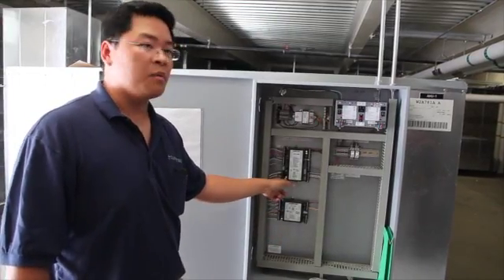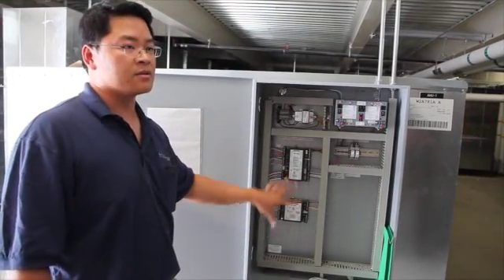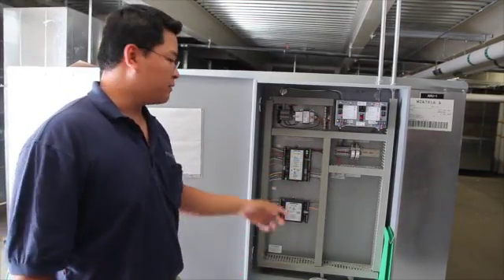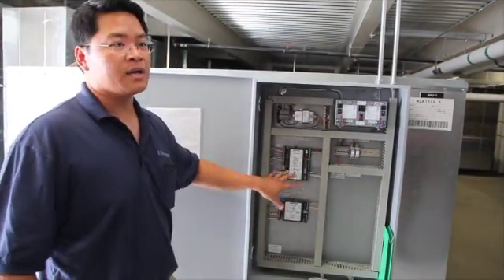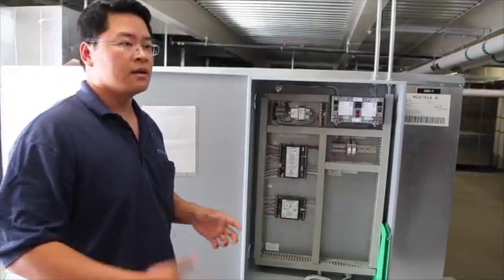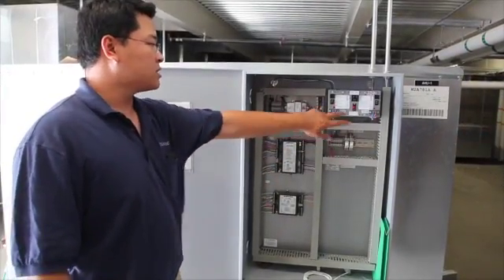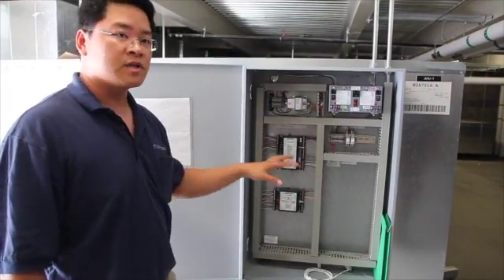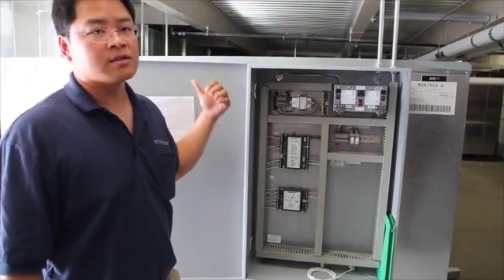This here is your important one. If it's not blinking three times, that means something is wrong. It's not talking to the brain of this building. If it's blinking twice, that means it's online, but it's not communicating to the front end. So the first thing, usually you want to try to reset. But if reset still doesn't bring back the unit for whatever reasons, then you want to make sure you call us.